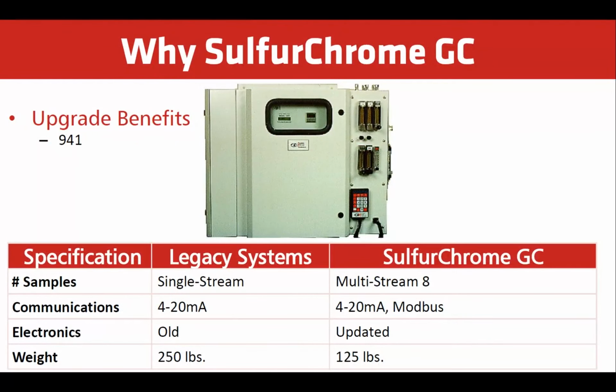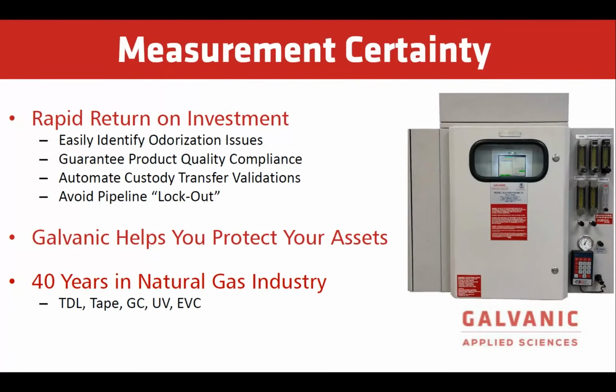The upgrade benefits: number of samples, single stream to multi-stream; communication, 4-20mA to 4-20mA with Modbus. Electronics in the legacy are old; Sulfur Chrome is updated. The weight: the oldest analyzer weighed about 250 pounds, the new one 125 pounds. Measurement certainty, rapid return on investment, identify odorization issues, product quality and compliance, automated custody transfer, validation, avoid pipeline lock-out.